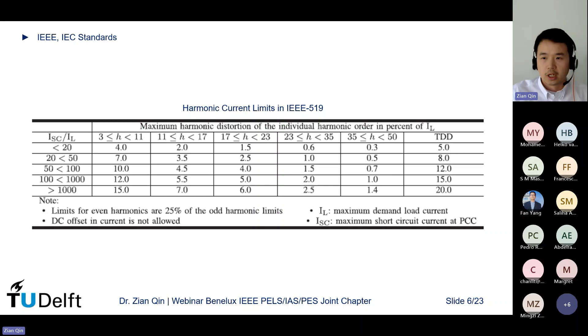Okay, no worries. Because what eventually matters is grid voltage distortion, right? When you inject the harmonic current into the grid, because the grid impedance is not zero, due to Ohm's law you will also indirectly induce a grid voltage distortion. But if you have a high short circuit ratio, which means a low grid impedance, you are allowed to inject more harmonic current. That's because even if you inject more harmonic current, due to this very low grid impedance, the grid voltage distortion is still low. So eventually, what matters again? What matters is grid voltage distortion.